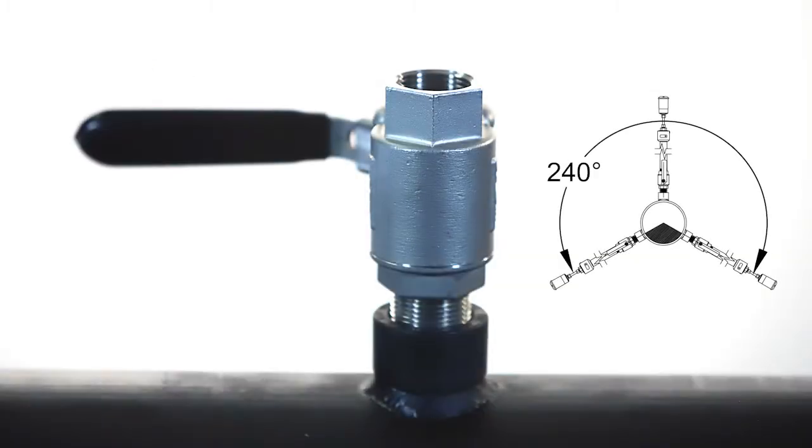A typical installation kit for steel piping systems is shown. The location requirements discussed in the previous slide should be taken into account before installing, and you should ensure that it is located on the top 240-degree section of a horizontal piping run.